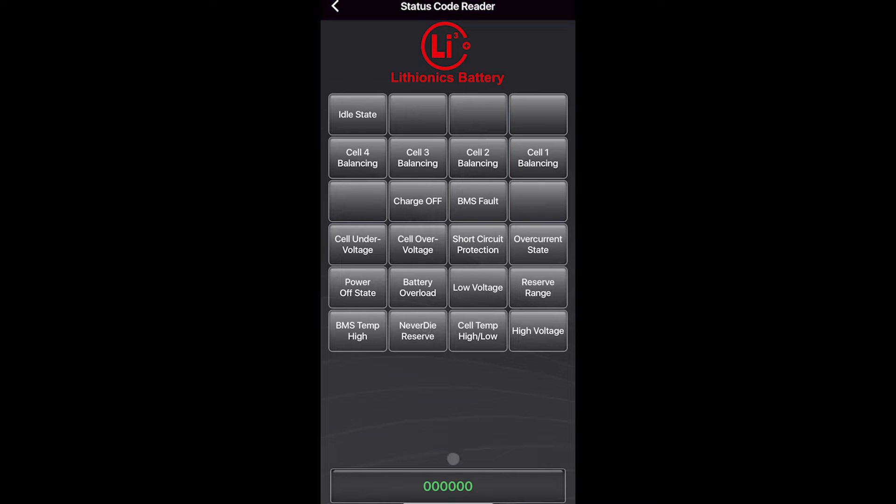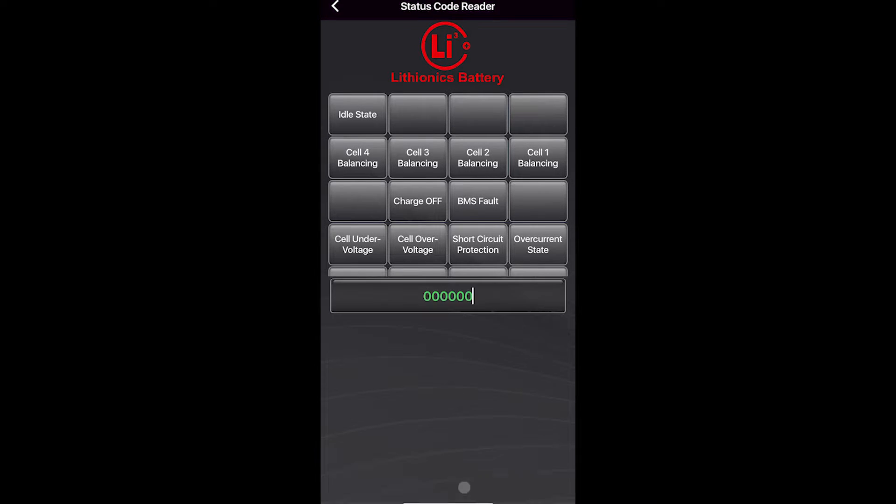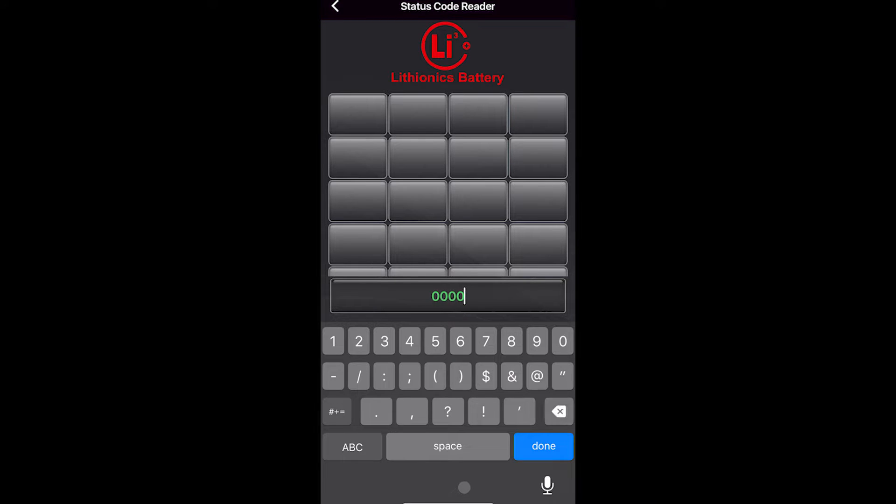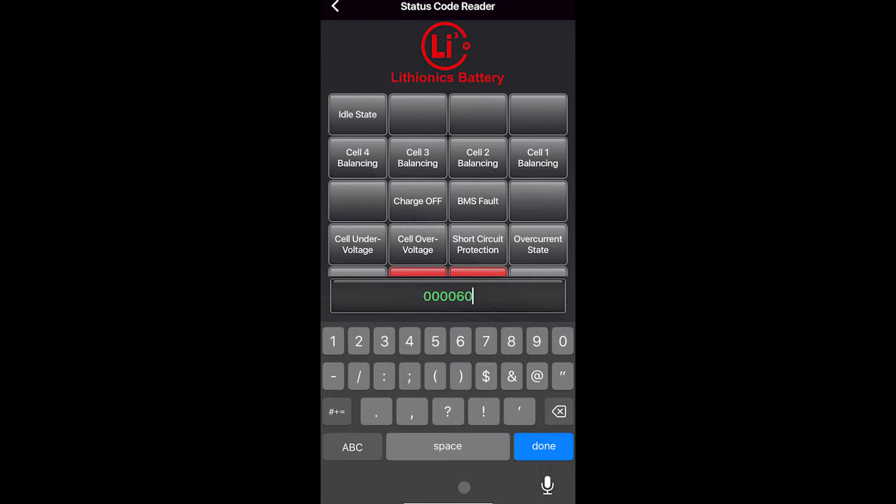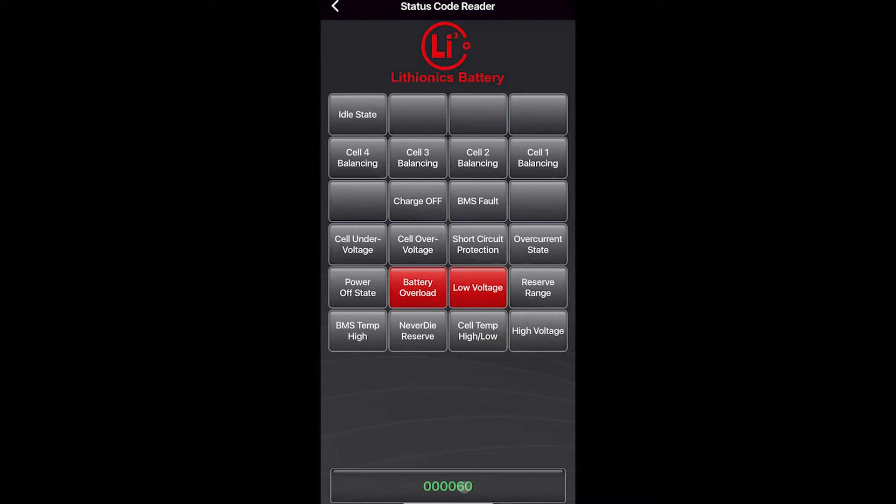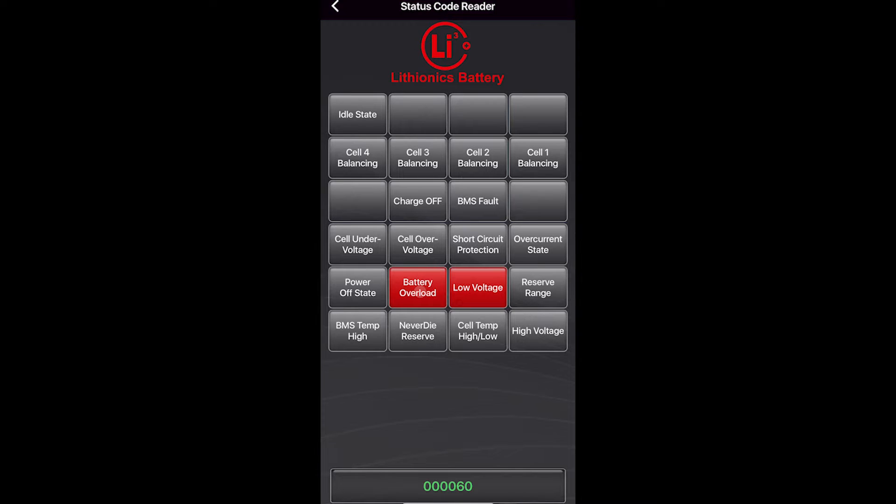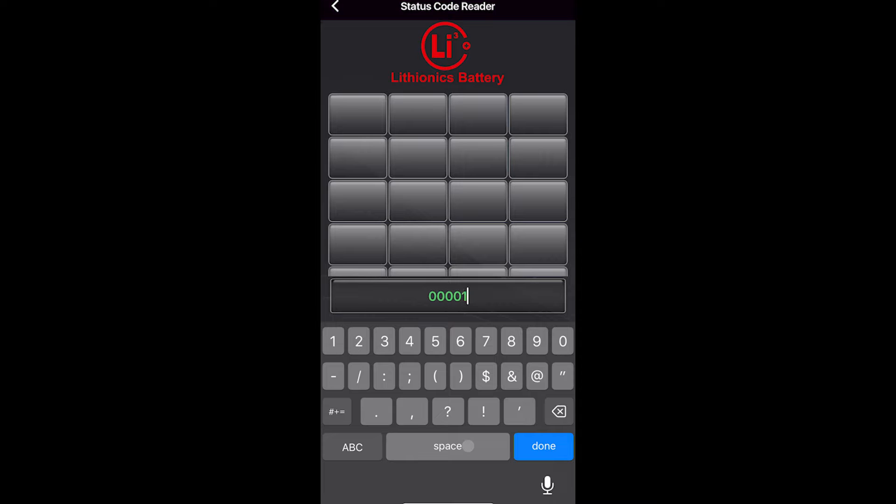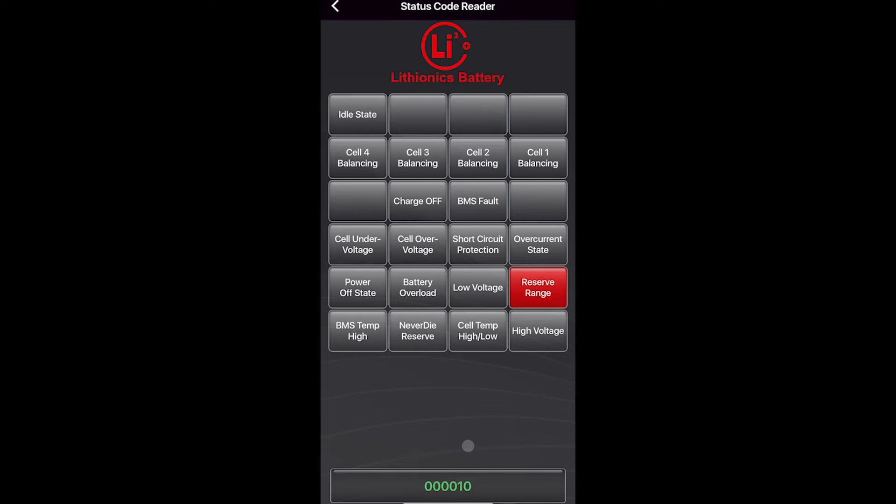If you have a code and you want to know what it means, you can click here and you can type a code that you've seen in the past and it will decode it for you and tell you what it is. So a 000060 is a battery overload with low voltage. If we did a 0010, that's reserve range.